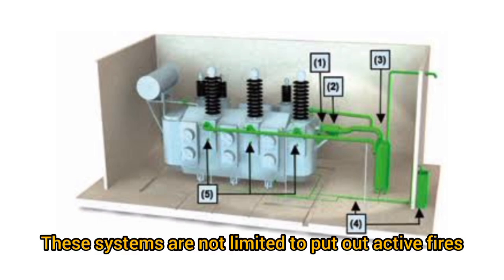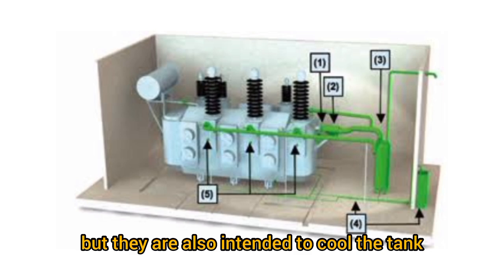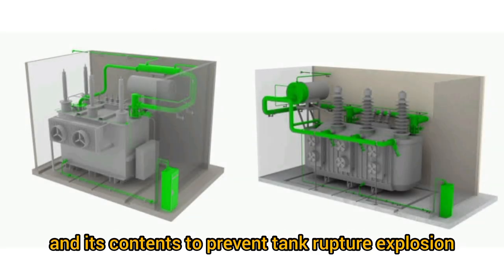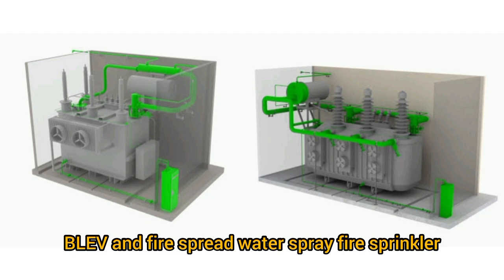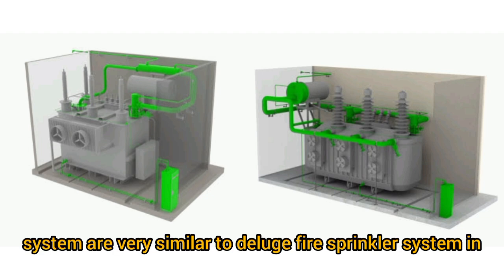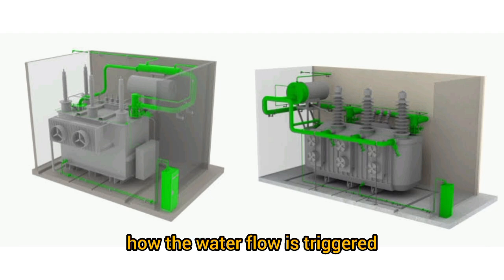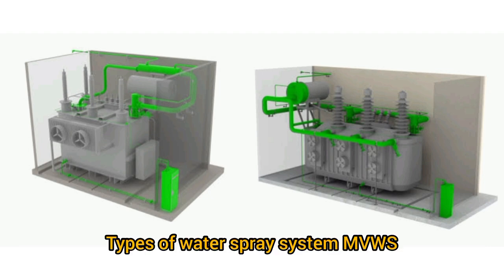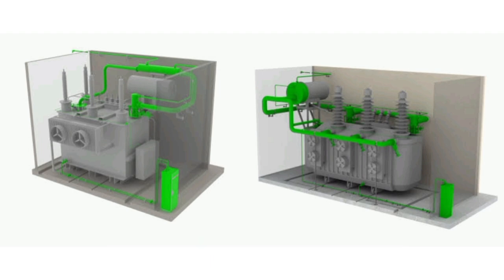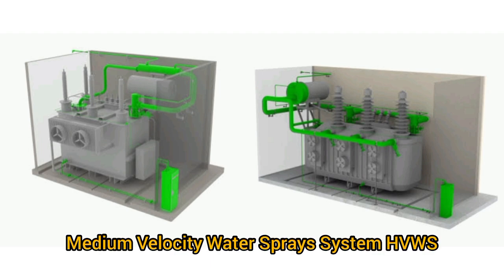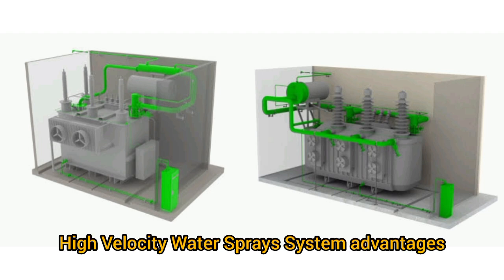These systems are not limited to putting out active fires, but are also intended to cool the tank and its contents to prevent tank rupture, explosion, BLEVE, and fire spread. Water spray fire sprinkler systems are very similar to deluge fire sprinkler systems in how the water flow is triggered. Types of water spray system: MVWS, medium velocity water spray system; HVWS, high velocity water spray system.